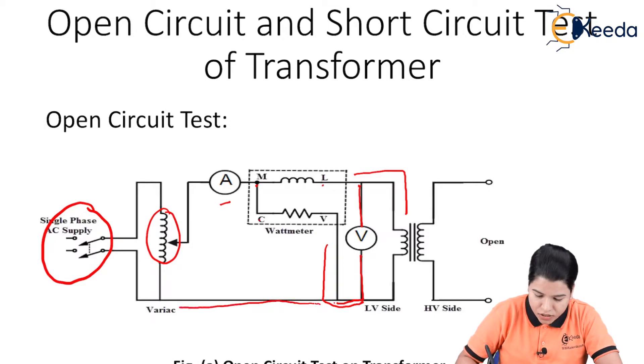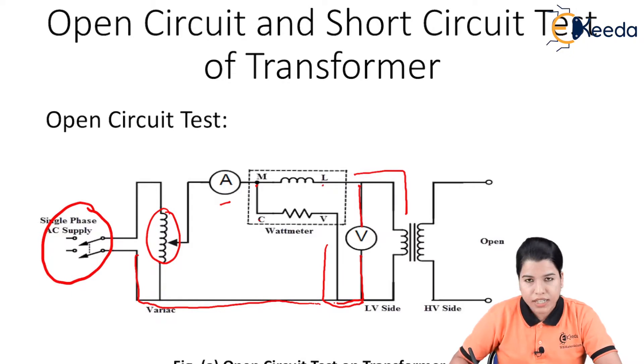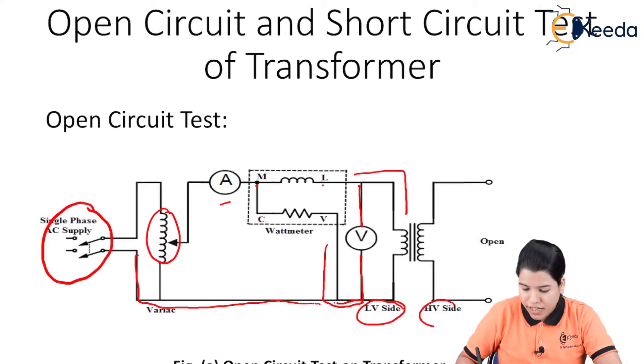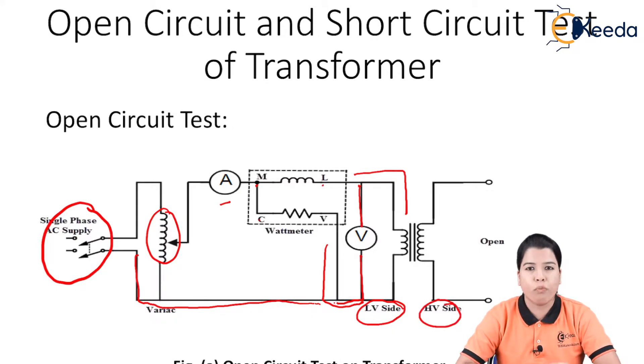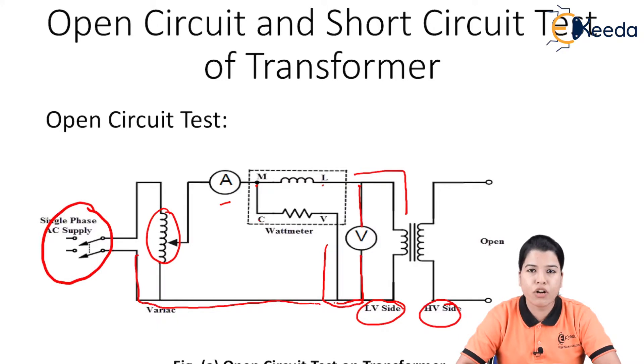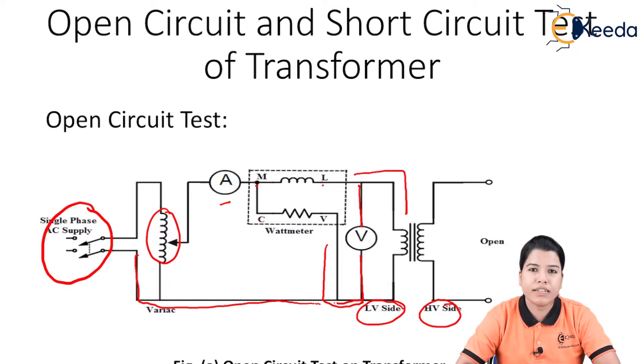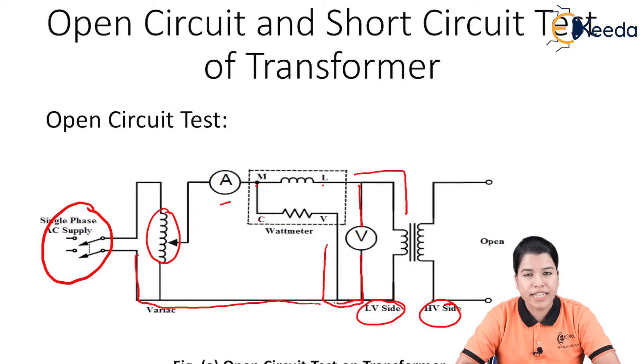The same terminal goes to the negative of the supply. The supply is given to the LV side, whereas the HV side is kept open. Hence, the secondary winding is open, and the test is called the open circuit test. To perform the test, we consider the rated voltage of the primary winding and vary the auto transformer until we get that rated voltage supplied to the primary winding.